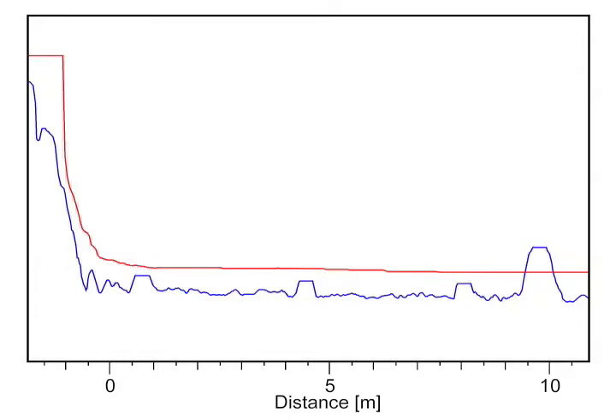This is the profile after setting the Narrow Echo Filter. You can see that the top part of all of the echoes have been cut off. It is important to use this filter only on solids applications. The true material echo for solids applications will always be wider than the obstruction echoes.